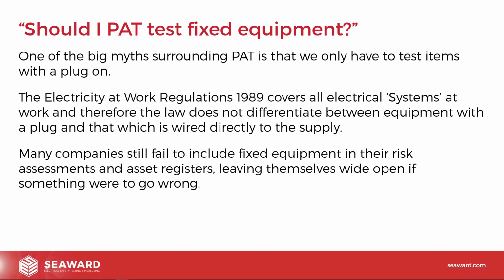So if somebody's doing the PAT testing, they'll say, well, I only do the stuff with the plug on. And somebody's doing the fixed wiring will say, well, we finish at the wall, we finish at the fixed wire, we finish at the spur or the isolator. And nobody's actually doing these bits in the middle. And there have been instances that we've come across where there's been accidents, there's been fires and things like that because that bit in the middle's not been looked at. And unfortunately, the duty holder is then in a sticky situation because they've missed that bit in the middle.